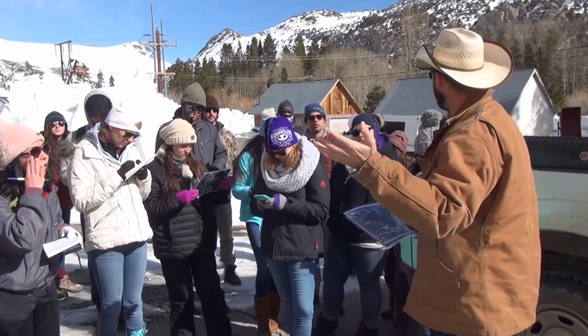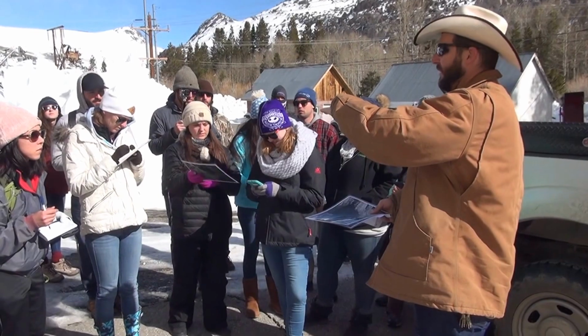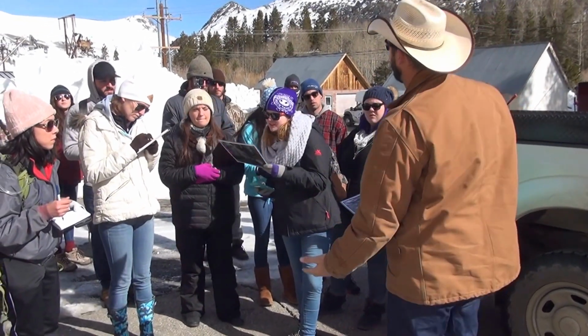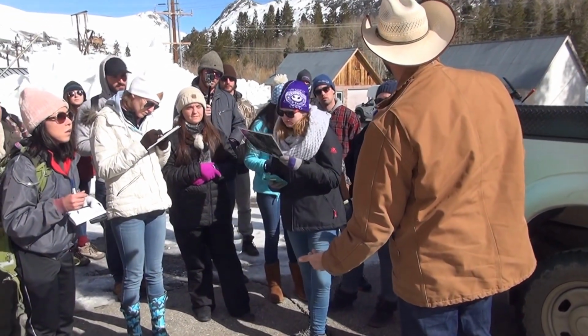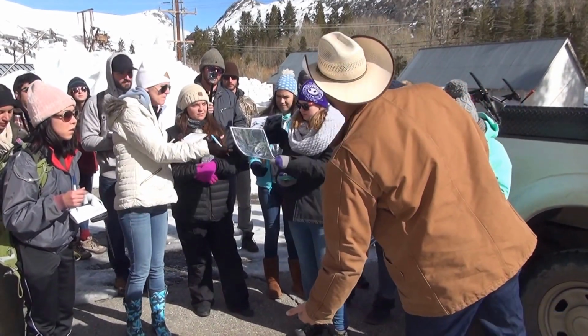So you get about 0.434 PSI per 1 foot of water. So if you put your hand in water 1 foot down, your hand is going to feel 0.434 PSI. Okay? 2 feet down, almost 1 PSI.